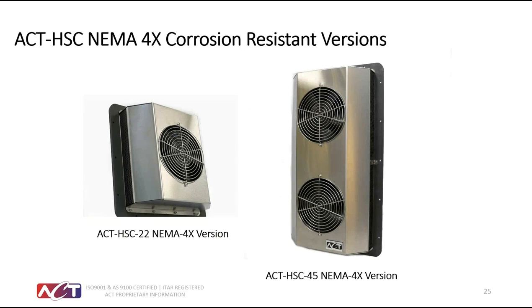Another very common request that we have, because of the types of environments that these systems are used in, either wash down, spray down, or they could be used in wastewater plants, we have a corrosion resistant model that is 3/16 stainless steel, and the actual bonded fins are treated with an epoxy coat, which is highly chemical and salt resistant. So that would be our NEMA 4X version. And those are very, very durable in those applications where you could have hydrogen sulfide gas. We all know when you get hydrogen sulfide combined with vapor or moisture, you get sulfuric acid, and that doesn't do well on metal surfaces. The fans themselves are potted on the outside, so they can be subjected to direct cleaning water spray and chemical spray.